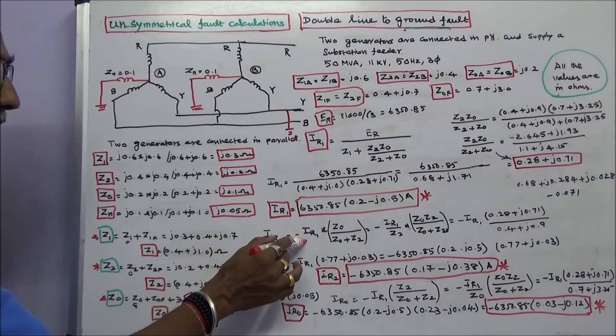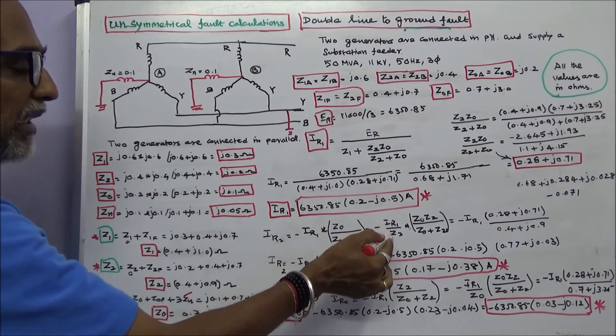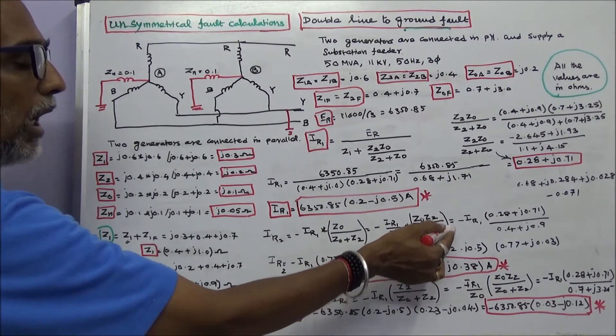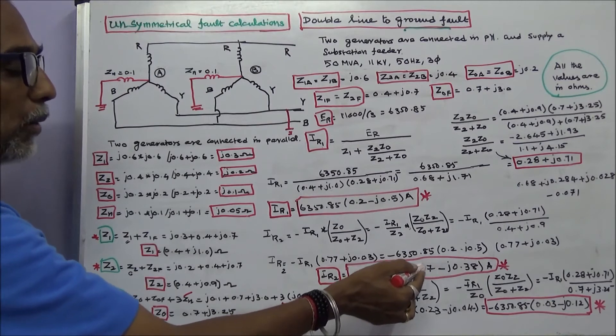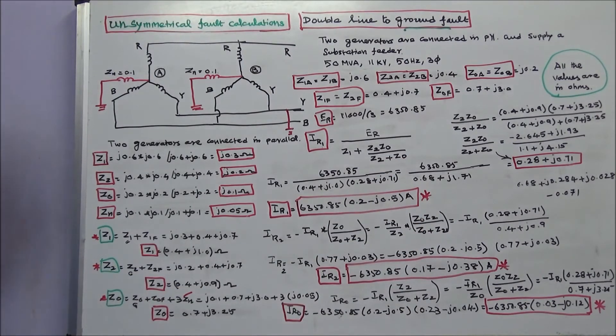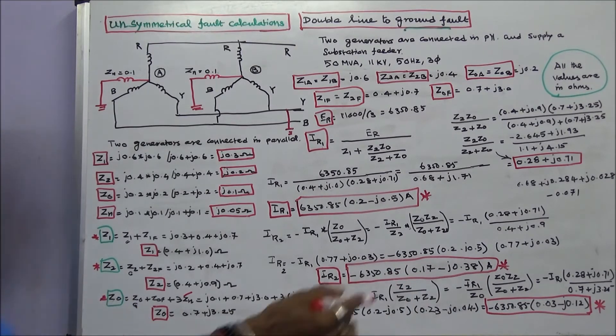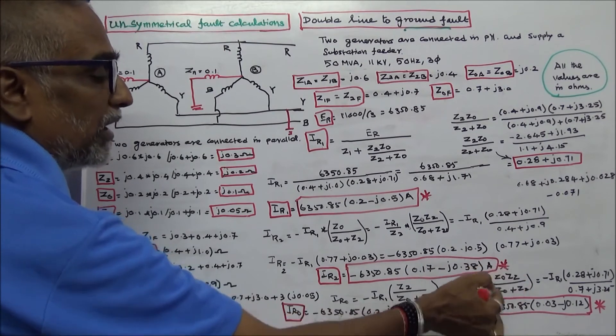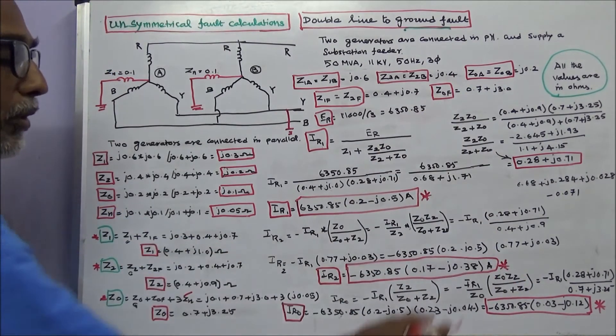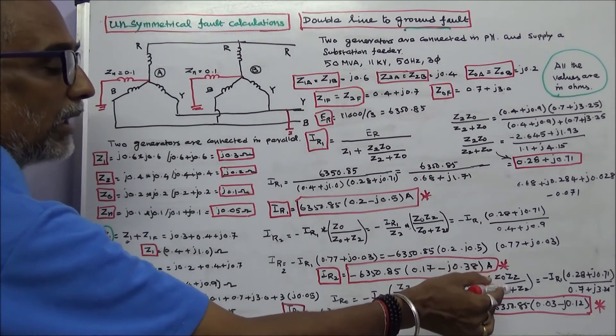IR2 equals minus IR1 times Z0 divided by Z0 plus Z2. Rewriting, IR2 equals minus IR1 divided by Z2 times Z0, times Z2 divided by Z0 plus Z2. Using the known value 0.28 plus J0.71 and substituting, IR2 equals minus 6350.85 times (0.17 minus J0.38). Similarly, IR0 equals minus IR1 times Z2 divided by Z0 plus Z2, giving IR0 equals minus 6350.85 times (0.03 minus J0.12).